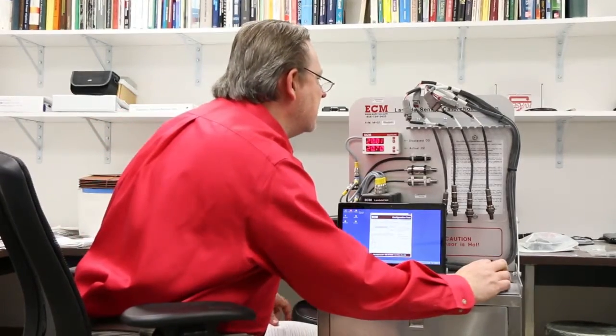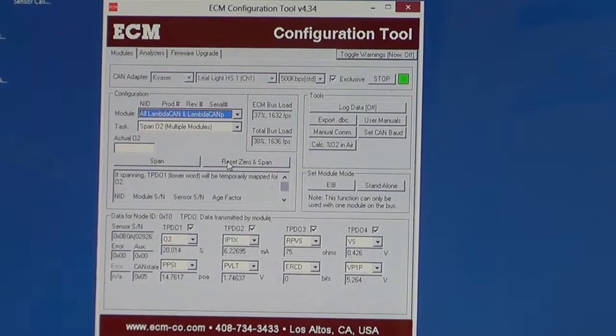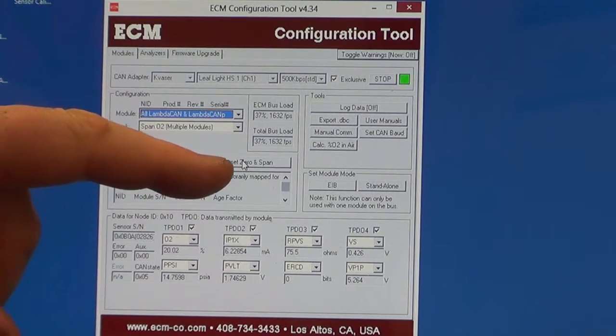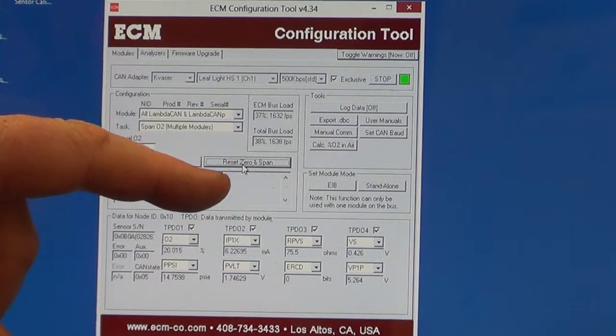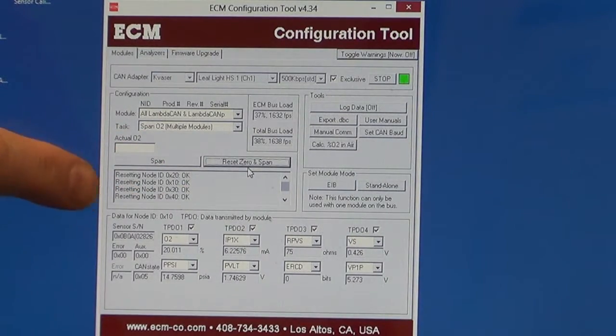So what you do is you click on the Reset 0 and Span, right there. You click on it, and in this field here, it states the progress, and after about 2 seconds, you see it says resetting node ID, 20's okay, 10's okay, 30's okay, and 40's okay. And that means that the Lambda CAN modules have not found any errors with the sensors.